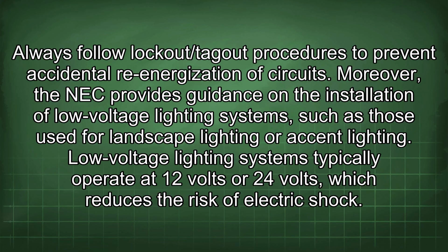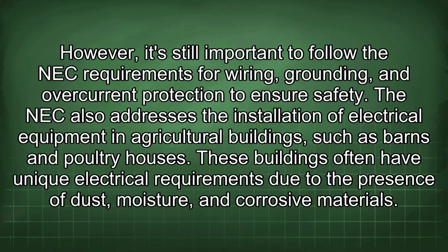Moreover, the NEC provides guidance on the installation of low-voltage lighting systems, such as those used for landscape lighting or accent lighting. Low-voltage lighting systems typically operate at 12 volts or 24 volts, which reduces the risk of electric shock. However, it's still important to follow the NEC requirements for wiring, grounding, and overcurrent protection to ensure safety.